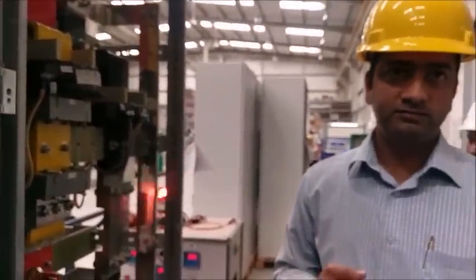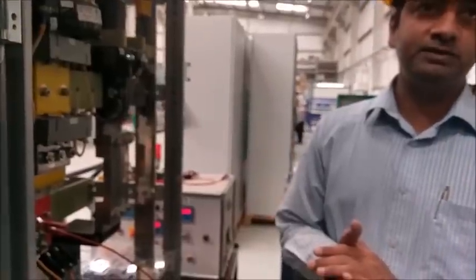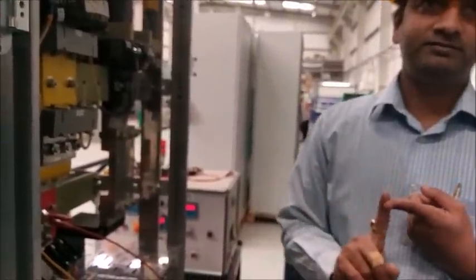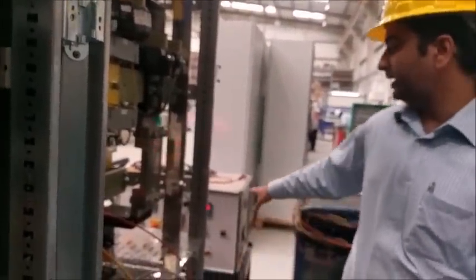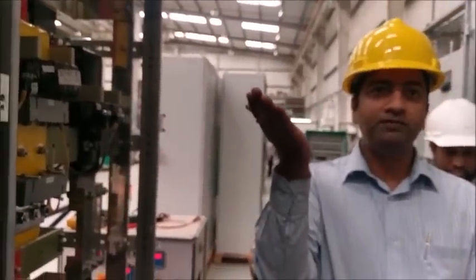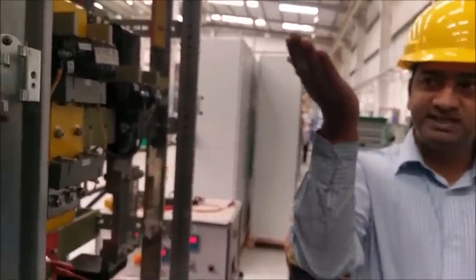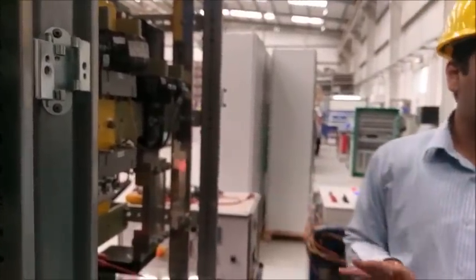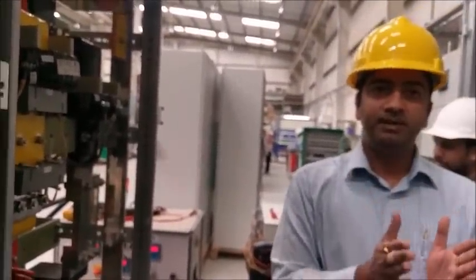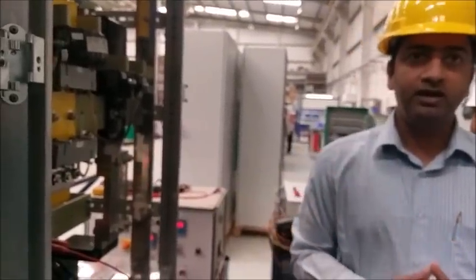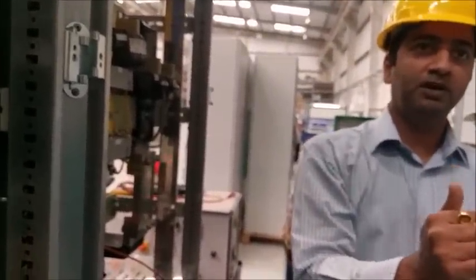Similarly, as I showed you for the Megger test, suppose there is an HV fail. This instrument turns the supply off, as if on a short. And if we have 2.5 kV, it is automatic. Once I start it, it gets the voltage from 0 to 2.5 kV. Then at 2.5 kV, the timer starts automatically, counting from 60 seconds to 0, and we apply 2.5 kV continuously. So for 1 minute this panel should withstand that much voltage. That means the power frequency test for phase to neutral is okay. Then after 1 minute, it will automatically decrease the voltage from 2.5 kV to 0. So this is the test.